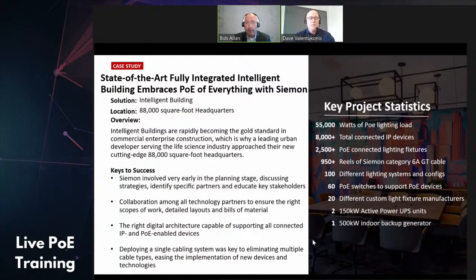They wanted a PoE-of-everything type scenario, and in doing that, they had over 55,000 watts of PoE lighting, over 8,000 connected devices in the building — and I should mention it's about an 88,000 square foot building. Because of that, we used over 950 reels of Category 6A cable. There were over 100 different lighting systems and configurations in the building, serviced by over 60 PoE switches. And the lights came from 20 different custom lighting manufacturers.